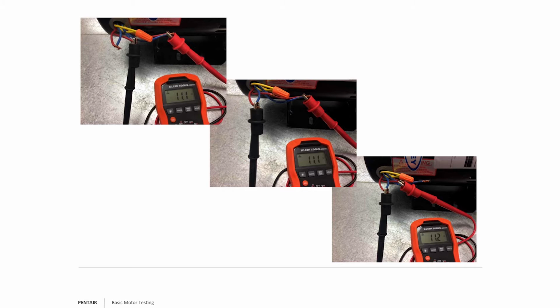And if you don't put good thermal protection on it, what can often happen is one leg gets weak or drops out. Say, for example, in that Y delta, that one line that's connected to T1 and T2 trying to make up a third leg, it might drop off, or it might just be completely out of sync. And what happens is then the winding 1 and winding 3 try to pick up extra amp load to make up for the work difference. And they'll get to the point where they get so hot, if you don't have thermal protection, that they flash, they burn. And you know, all motors run on blue smoke. You let the blue smoke out, the motor's done.